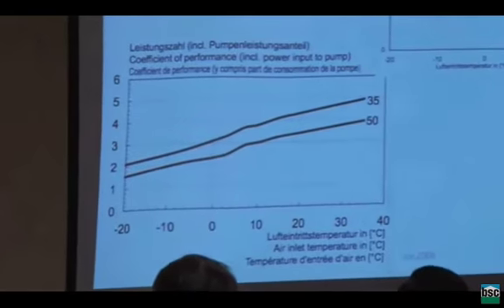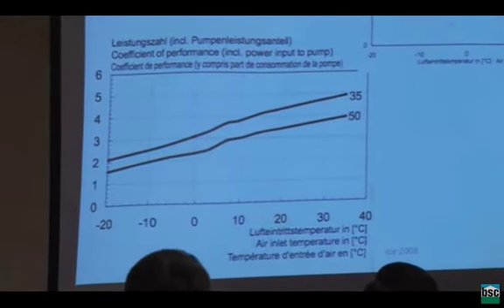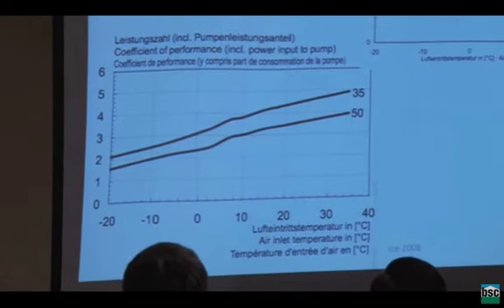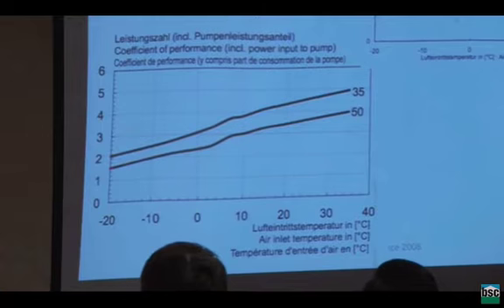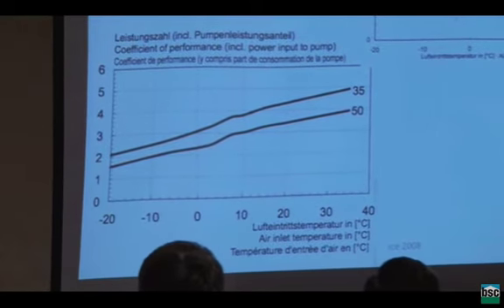The problem here is that as you try and produce really hot water, your efficiency really drops off quickly. So if you're willing to live with water that's 105 degrees or 95 degrees, your efficiencies are on par with an air-to-air heat pump. As you start asking for warmer water than that, say you want 120 degree water, then the efficiency starts falling off. And the left bottom there is the COP as a function of outdoor temperature, minus 20 degrees Celsius, meaning roughly minus 4 Fahrenheit. If you produce water that is 95 degrees, you get a COP of 2. If you produce water that is about 130, 125 degrees, your COP drops to 1.5 at those temperatures.